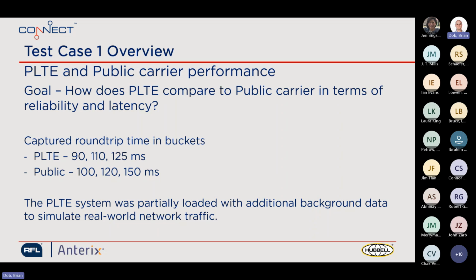The reason for that is that the latencies are a little different between the two systems, and we wanted to characterize the performance more accurately, so setting the time buckets a little differently helped in that regard. The private LTE system is a little bit faster than the public system, and we'll see that on the next slide in the results. Also note, like Jason said earlier, we do have background traffic on the network. The private LTE system, in addition to the direct transfer trip communications, was partially loaded with some additional background data, to simulate a real world scenario as best we can in a lab environment.